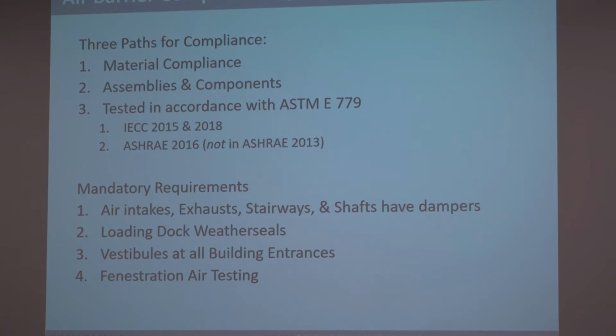There's a material compliance method. You install one of the materials, and I'll go through those in a minute. Assembly and components compliance method, or whole building testing. And after I go through some of the mandatory requirements, I'll come back to these compliance path methods in a little bit more detail. So there's mandatory requirements for basically any of your big leakers: the air intakes, exhaust, stairways, shafts, things that we sort of know are big air movers must have dampers and have to be clearly closed off.